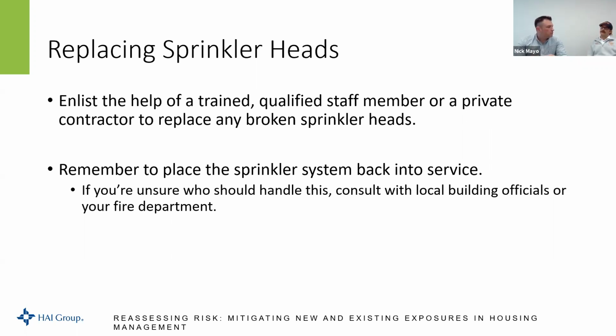Paul, offhand, do you know how many spare sprinkler heads within a building people need to have, depending on the type of building they have? Yeah, so depending on the size of your building and the number of heads you have, we kind of do it on a numbers basis. So 0 to 300 heads, you're going to want to have 6, maybe 7 spare heads. 300 to 1,000, you're going to want to double that to 12. And then 1,000 or greater, you're going to want 24 heads.